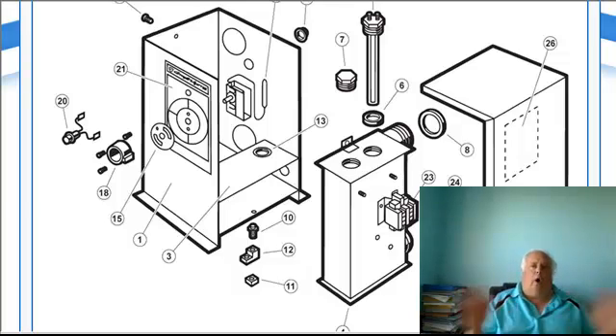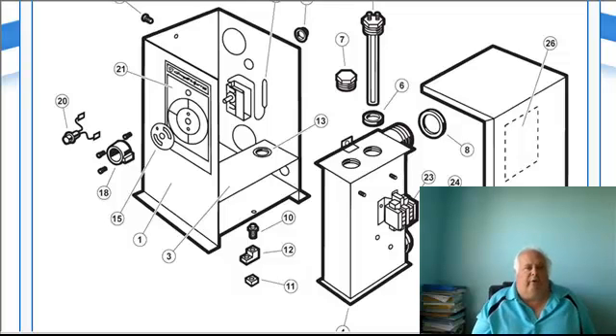With power off, you can ohm out a lot. If you got your pump running, these 2 wires here should read normally closed. Alright, so you should read a dead short. You don't have to read a dead short with voltage off, but with pump on, you should read a dead short. You either don't have the proper voltage, the proper flow rate, or you got a bad switch. Then going from there, you go to your high limit switch. Going from your high limit switch, you go to either one, well, you would have 2 high limit switches, I think. If it was a dual, then you have 2 wires going to your heater.